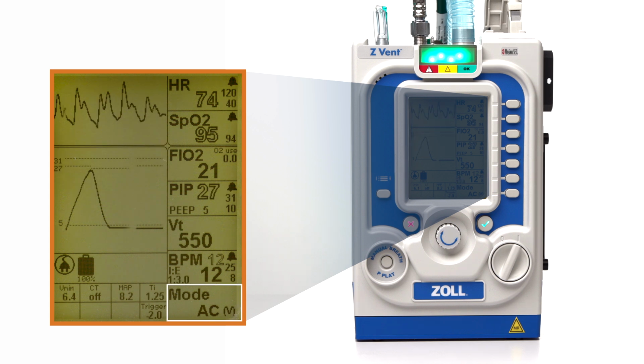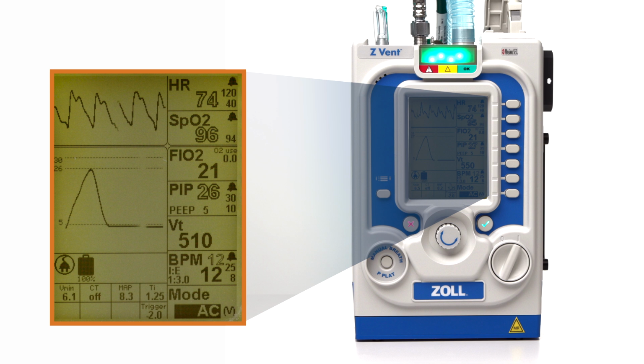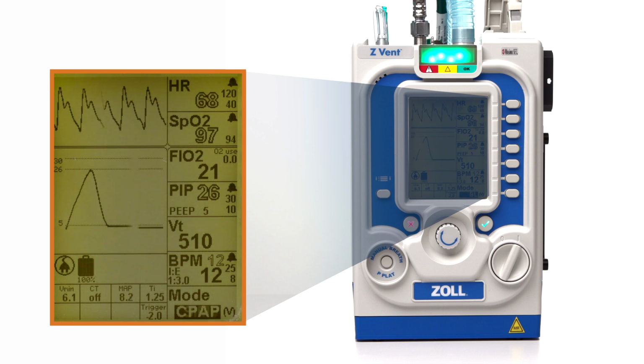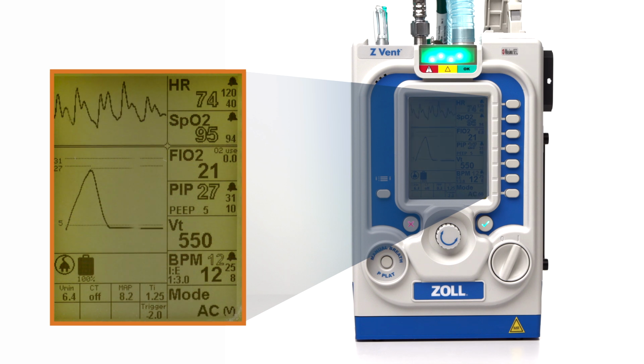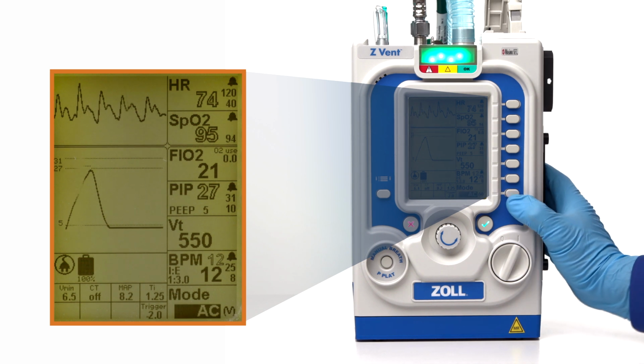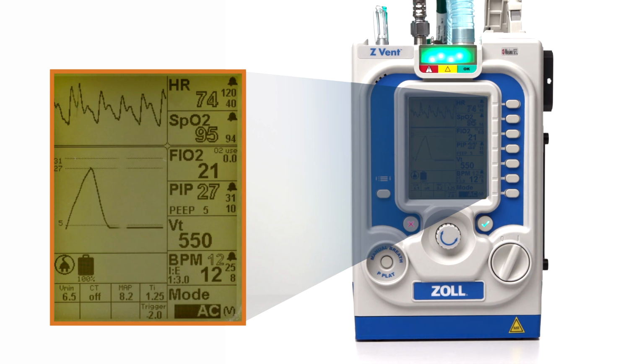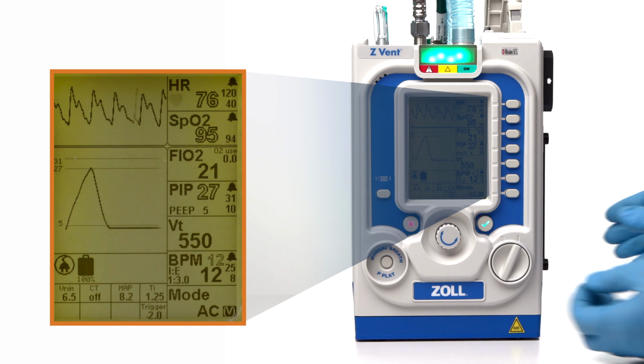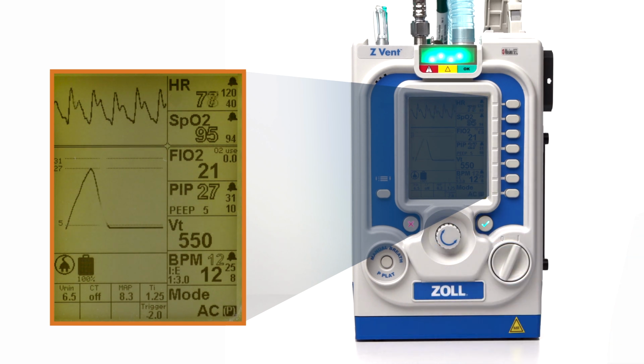The seventh parameter window is ventilation mode. The Z Vent has four primary ventilation modes: assist control, SIMV, CPAP, and bi-level. Press the parameter button once to change the desired ventilation mode and twice to change whether to operate in volume-targeted breathing mode or pressure-targeted breathing mode.